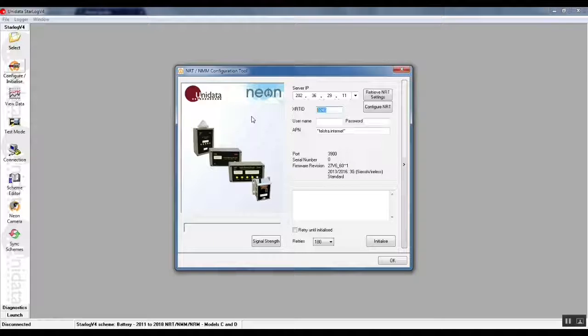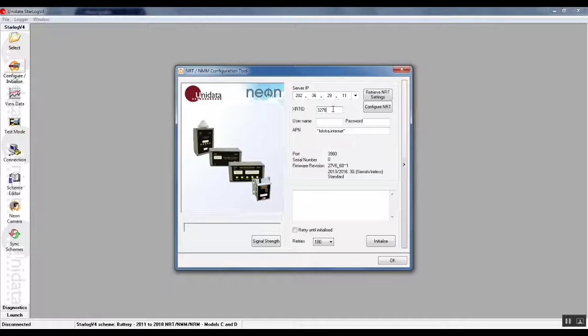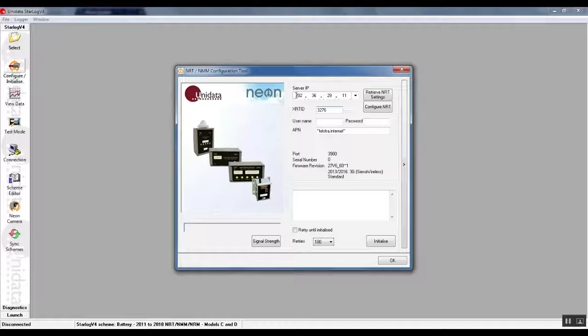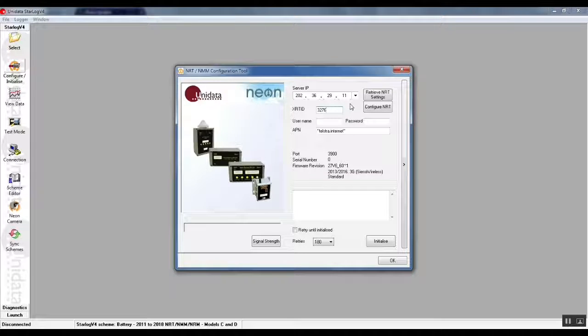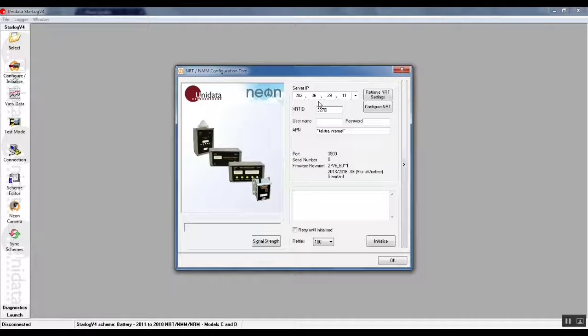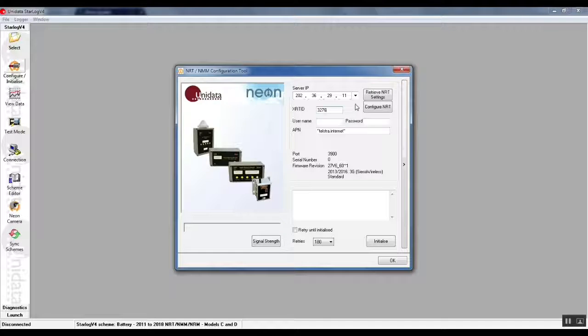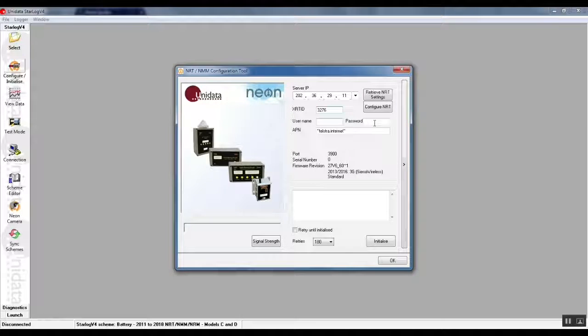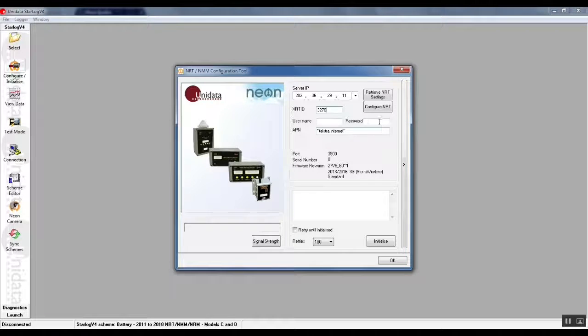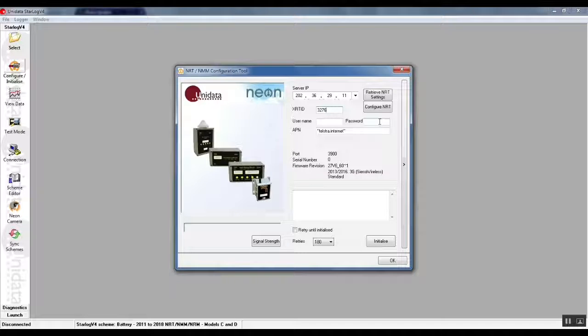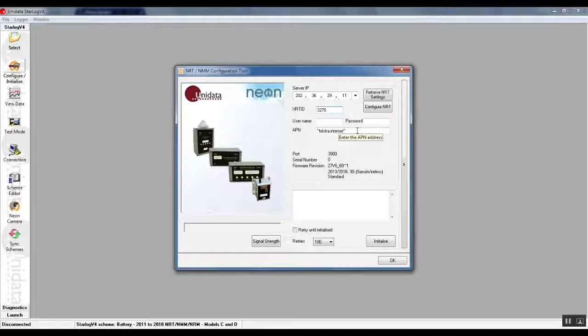Most important thing we need to change is the NRT ID. That will come from the factory probably set to zero already, so we have to enter the NRT of the site that we just added which was 3276. We also have to make sure that the server IP address is correct for the neon service that your NRT is on. neon.unidata.com.au, the IP address is 202.36.29.11. This particular NRT has already been set up but if yours isn't you would have to set that to the right IP address. Username and password is not required, that's not the neon service username and password, that's the SIM cards username and password. They are normally unlocked so you don't need a username and password.